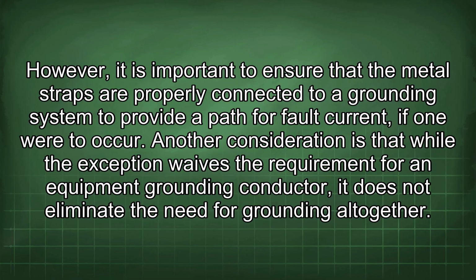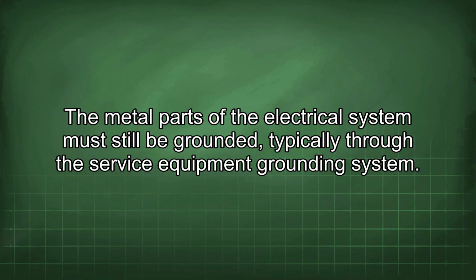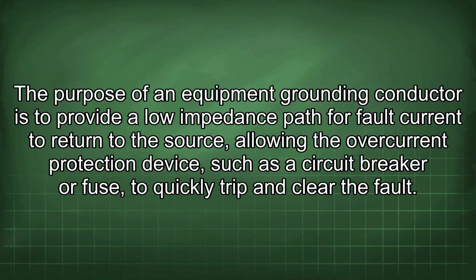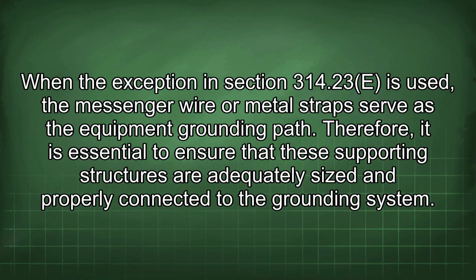Another consideration is that while the exception waives the requirement for an equipment grounding conductor, it does not eliminate the need for grounding altogether. The metal parts of the electrical system must still be grounded, typically through the service equipment grounding system. The purpose of an equipment grounding conductor is to provide a low impedance path for fault current to return to the source, allowing the overcurrent protection device, such as the circuit breaker or fuse, to quickly trip and clear the fault. When the exception in Section 314.23(E) is used, the messenger wire or metal straps serve as the equipment grounding path. Therefore, it is essential to ensure that these supporting structures are adequately sized and properly connected to the grounding system.